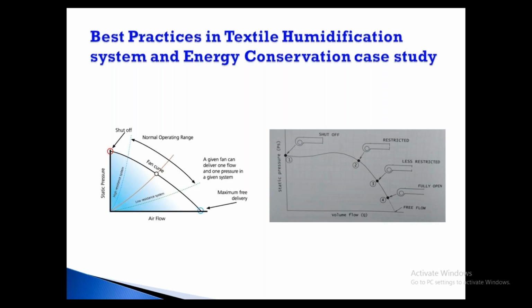So at the best operating point, which operating point we can operate the fan, that we have to decide based on whatever is given by the fan manufacturer, or we have to find out if the fan is designed to deliver this much air quantity at a particular pressure. So we have to first run the fan and see what the volume is by measuring with the anemometer. We can take it in the humidification plant, after the eliminator, and find out the area. Of course, volume of air is nothing but area times speed of the air, that is, velocity of the air. So area in meters or feet, we can get the area of the flow path, and we can find out with the anemometer what the speed of the air coming in is, in meters per second or feet per minute. So we have to take the average velocity.